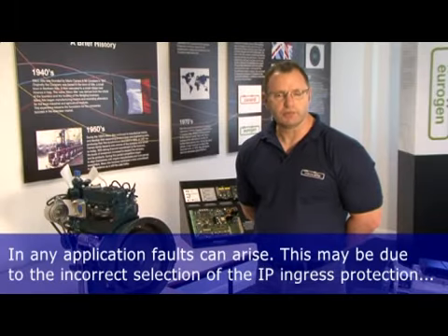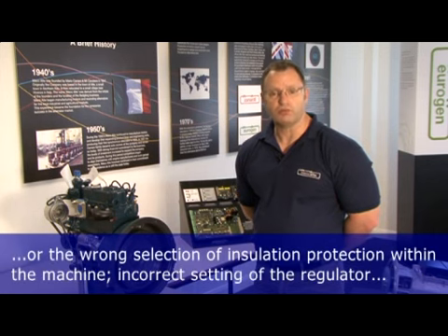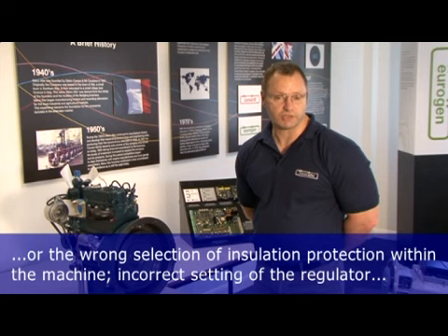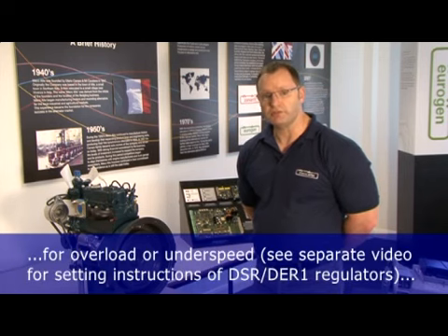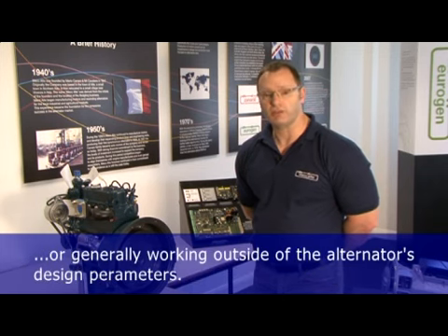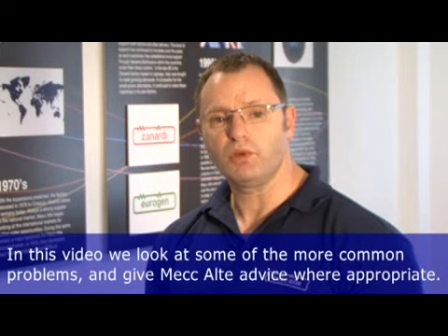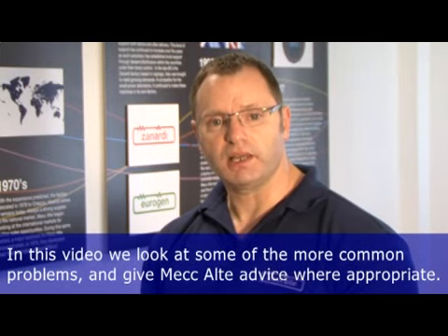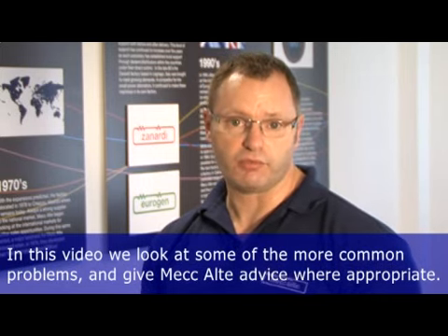In any application, faults may arise. This may be due to the incorrect selection of the IP ingress protection for the machine, the wrong selection of the insulation protection system within the machine, incorrect setting of the regulator for overspeed and underspeed, or generally working outside of the alternator's design parameters. In this video, we look at some of the more common problems and give Mecc Alte advice where appropriate.